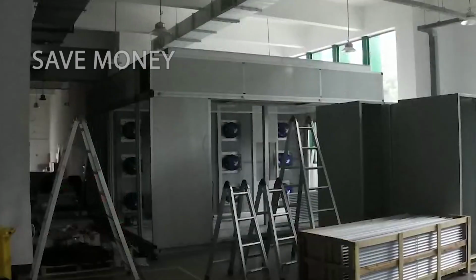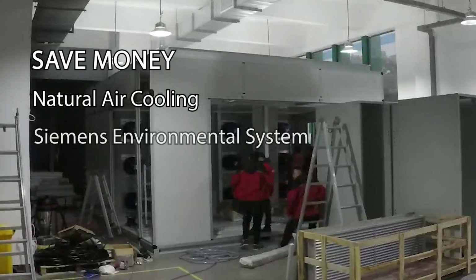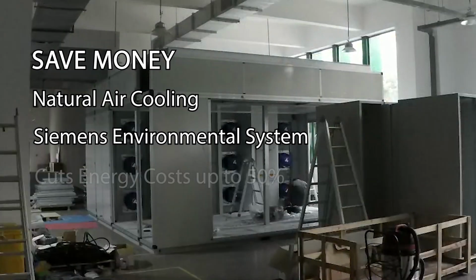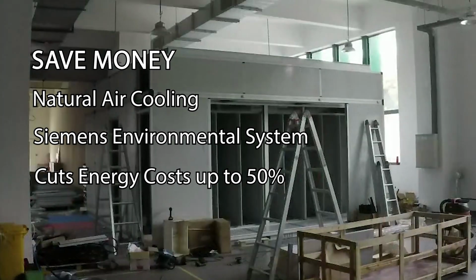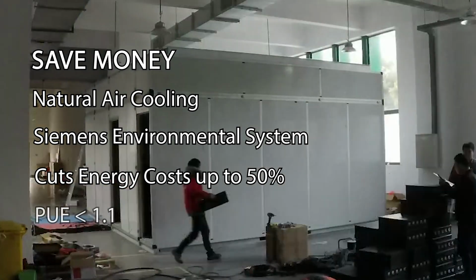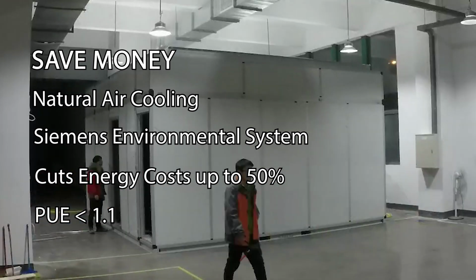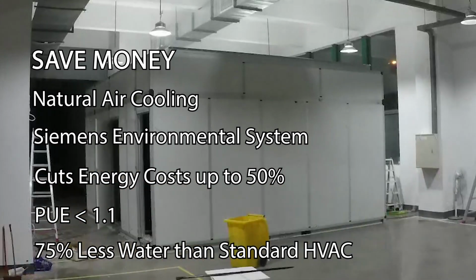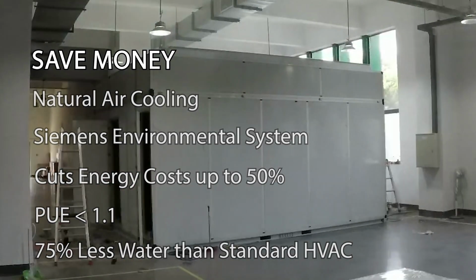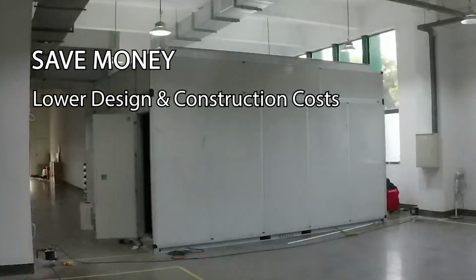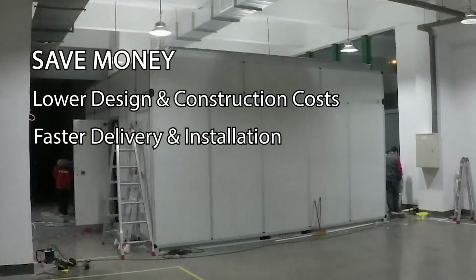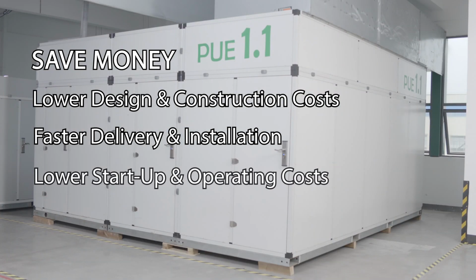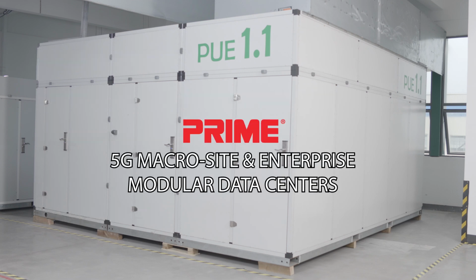Prime's MDCs save money. Natural air cooling with Siemens Environmental Systems programmable logic control cuts energy costs by up to 50% over standard HVAC cooling systems with a PUE of 1.1 or less. The supplemental evaporative cooling uses approximately 25% of the water needed for traditional water-based HVAC. You save on design and construction costs, shorter delivery and installation time, lower electricity and energy costs, lower startup and operating costs, increase your ROI. With prefabricated models for 5G macrosites and enterprise applications, Prime can help you deploy faster, save money, and scale up quickly.